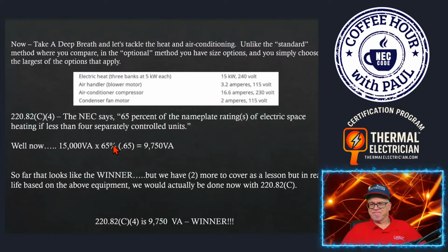The next one, C4. The NEC says 65% of the nameplate rating of the electric space heating if less than 4 separately controlled units. Okay, so in our case, this looks like the winner, right?